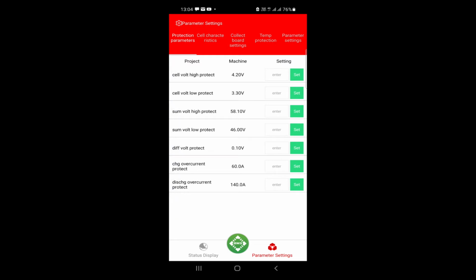Overcurrent I have adjusted to 60 ampere. This will depend on the number of parallel batteries you have in your battery pack. Discharge overcurrent protect I have set to 140 ampere, so that also depends on the number of parallel batteries you have in your battery pack. So these are the ideal settings for the lithium ion Leaf module battery pack. Cell characteristic also you can set, but it does not mean much to the settings of your battery. So these are the ideal settings.